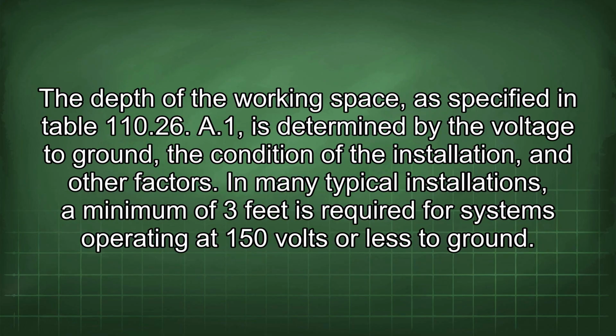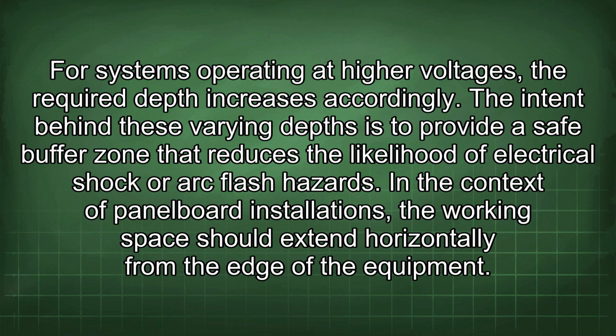The depth of the working space, as specified in Table 110.26(A)(1), is determined by the voltage to ground, the condition of the installation, and other factors. In many typical installations, a minimum of 3 feet is required for systems operating at 150 volts or less to ground. For systems operating at higher voltages, the required depth increases accordingly. The intent behind these varying depths is to provide a safe buffer zone that reduces the likelihood of electrical shock or arc flash hazards.